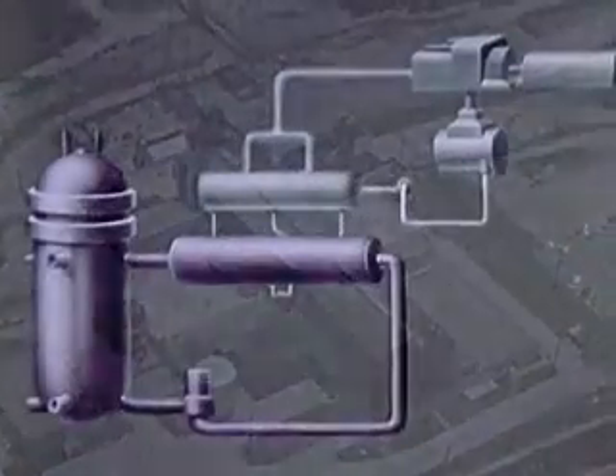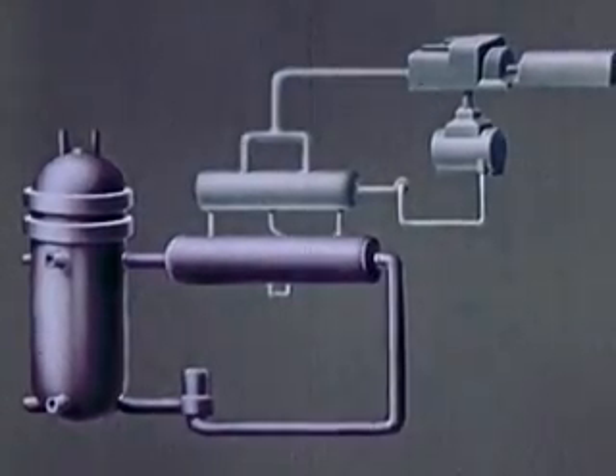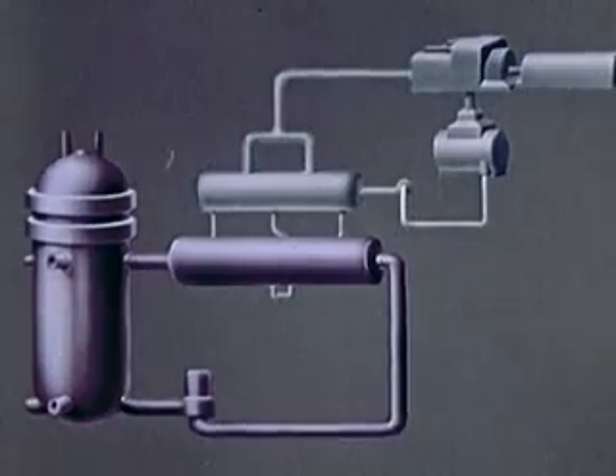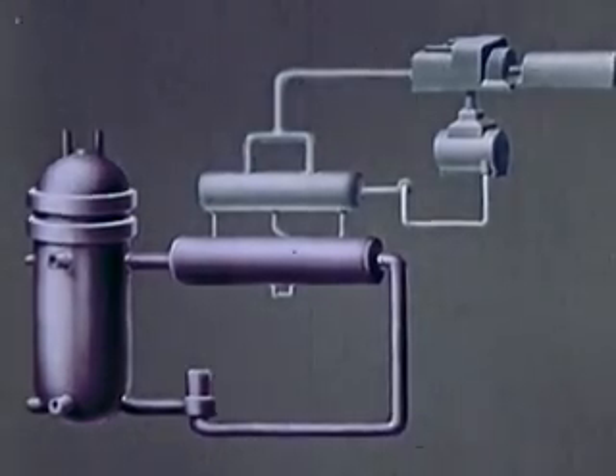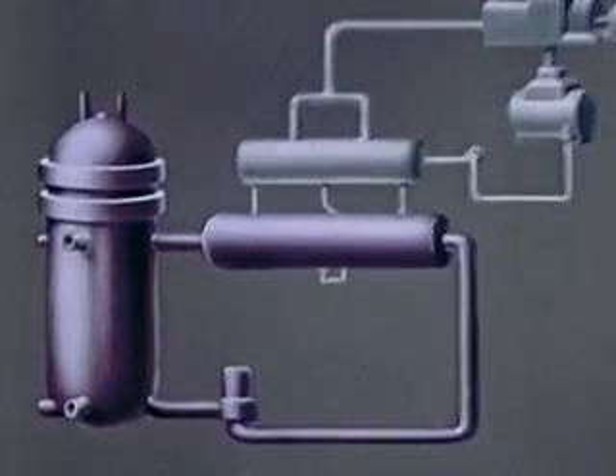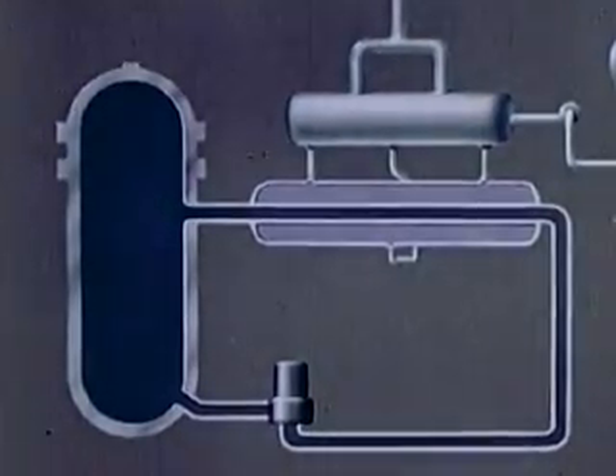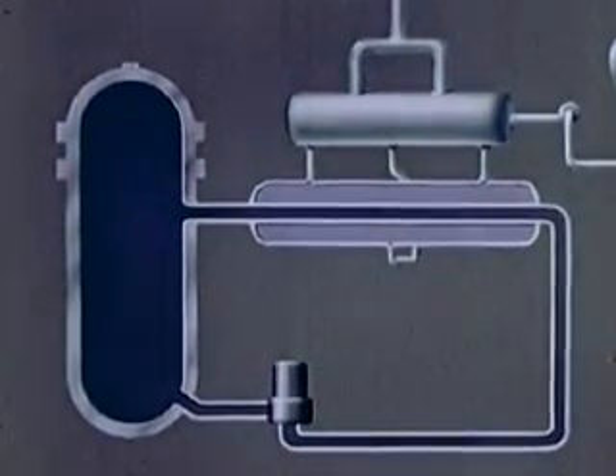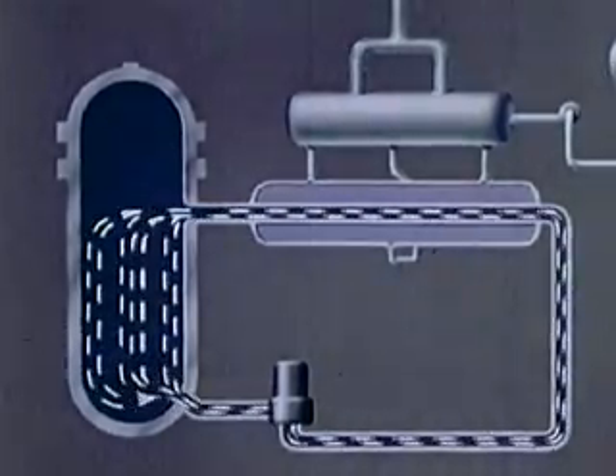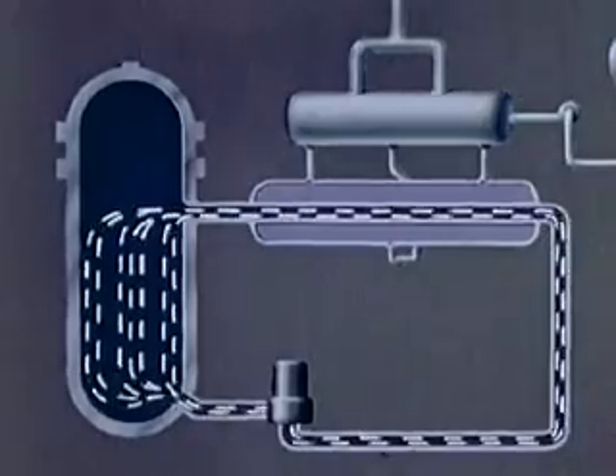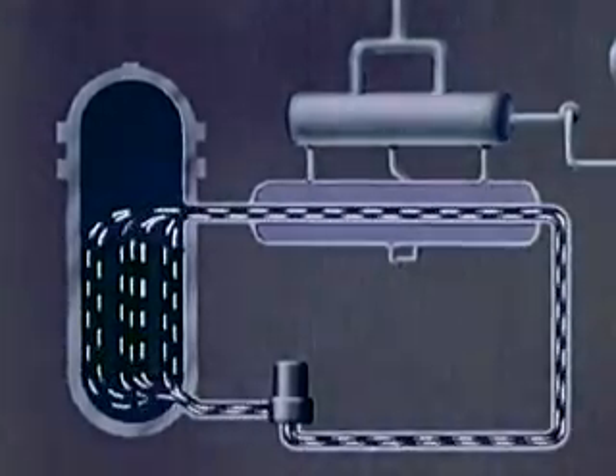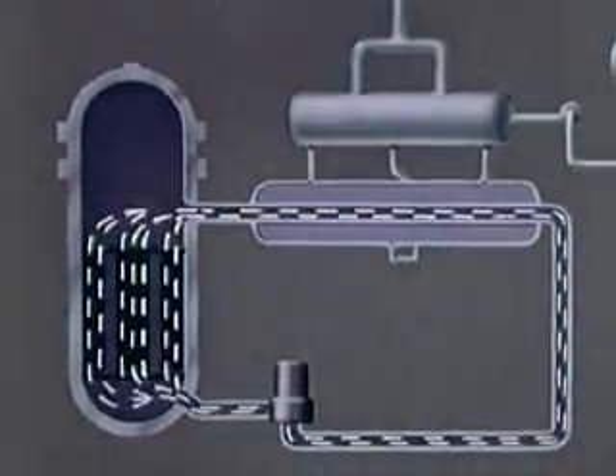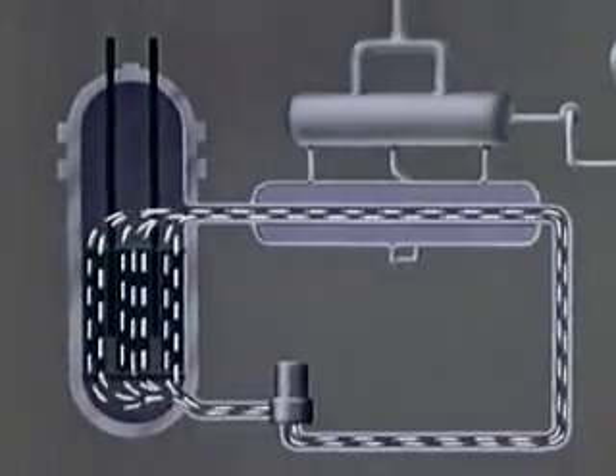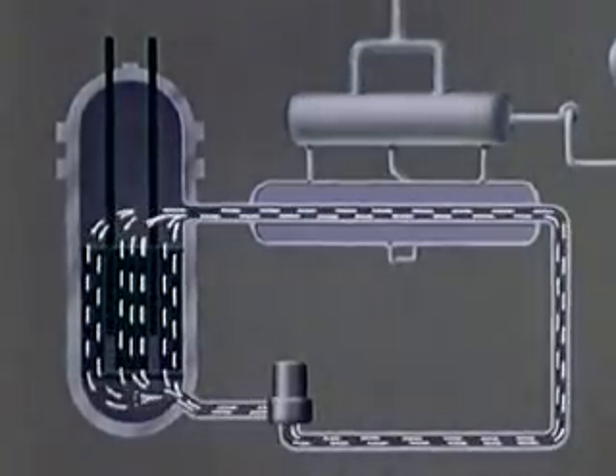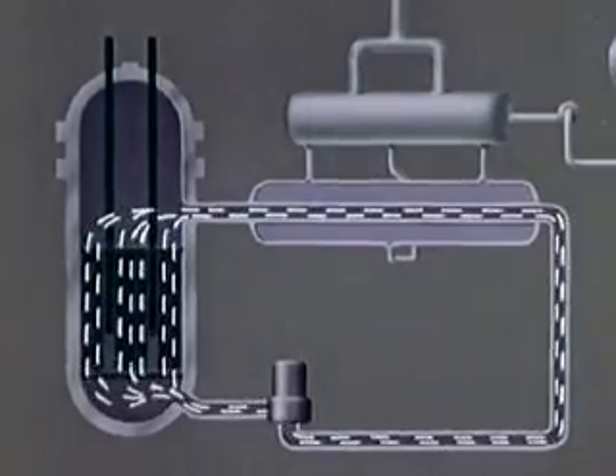Basically, the pressurized water reactor station operates on a simple principle, embodying a primary and a secondary heat transfer system. In the primary system, ordinary water of high purity, kept under pressure to prevent boiling, is pumped through the reactor. This contains uranium fuel and control rods. The water serves as a neutron moderator as well as a heat transfer medium.